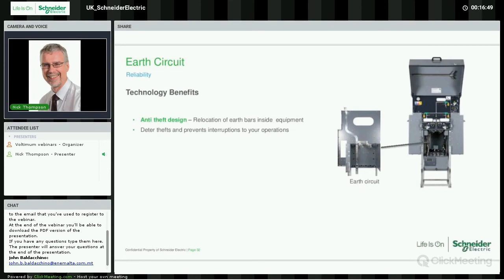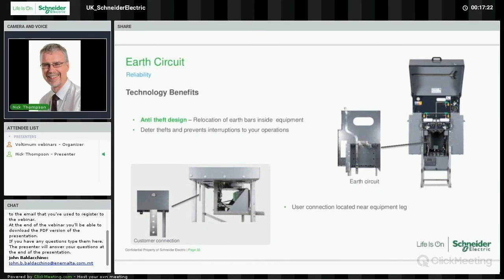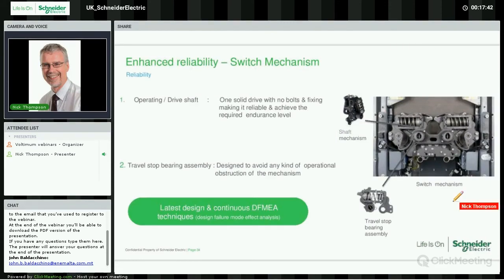Earthing, where you connect onto the substation earth. There's still an earth connection there, but it's actually been moved to make not only the unit look a little bit neater, but it's also removing the opportunistic thief, where copper theft inside a substation is a real serious problem. So the main earth circuit is hidden behind the main steelwork with a bar which will stick out at the bottom of the unit, where the substation earth will be terminated, along with the flexible braids for bonding on the gland plate, glands and transformer. So that's a positive move. There will still be anti-vandal fixings available for those that require them.